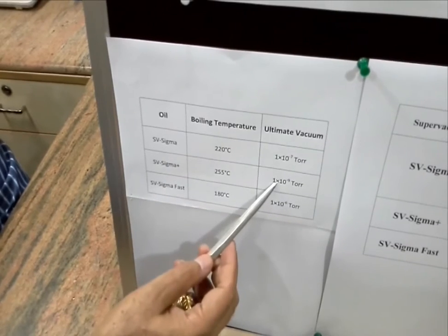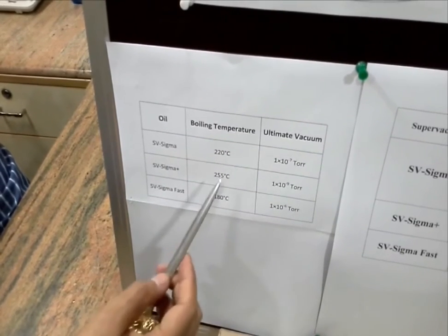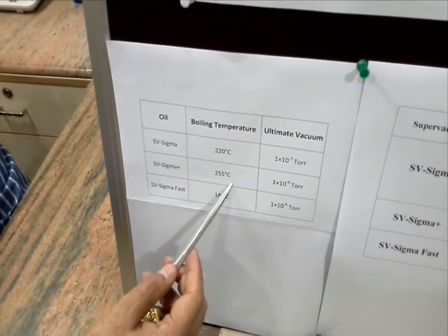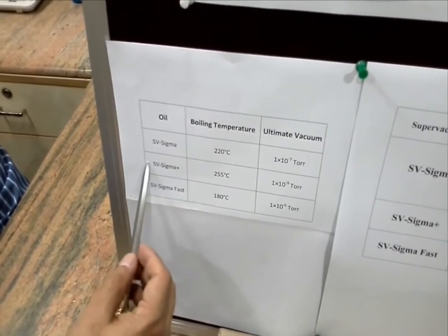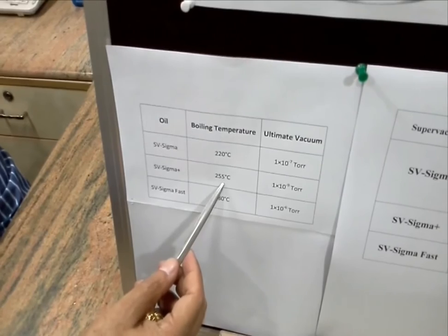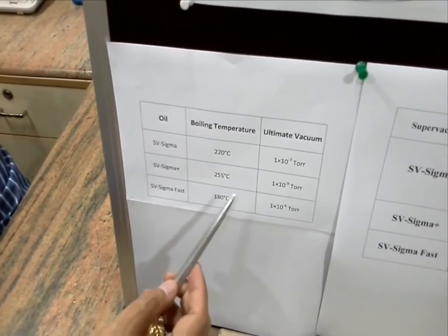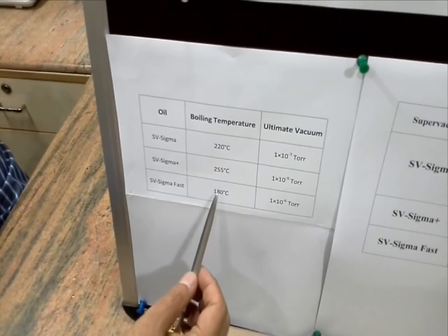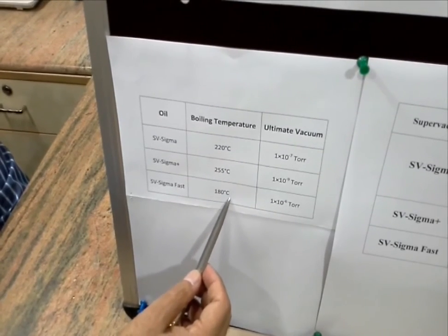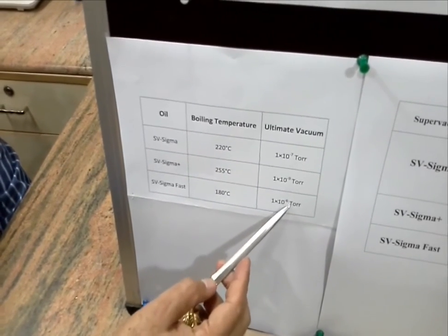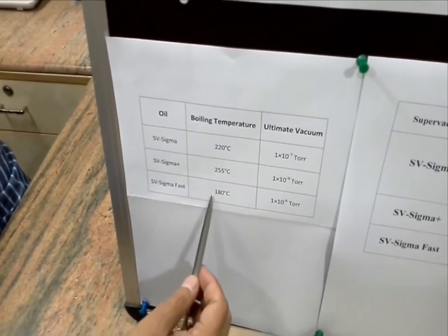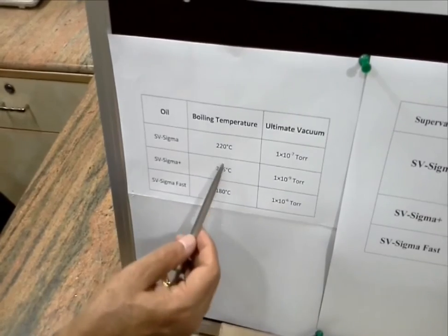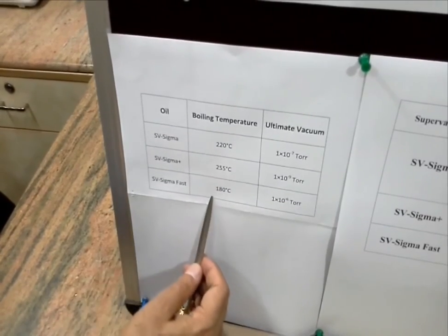However, if we require a vacuum even above this — for example for research purposes — we could always go for an oil with a higher boiling temperature, say about 255 degrees centigrade. Supervac manufactures SV Sigma Plus, which meets this criteria. Or sometimes vacuum speed is extremely important and vacuum level is not that important, so we go for an oil with an even lower boiling temperature of 180 degrees centigrade, which gives a vacuum of around 10 to the power of minus 6 Torr, but that doesn't matter because we are getting the vacuum very, very fast. So diffusion pump oils are manufactured with these three boiling temperatures.